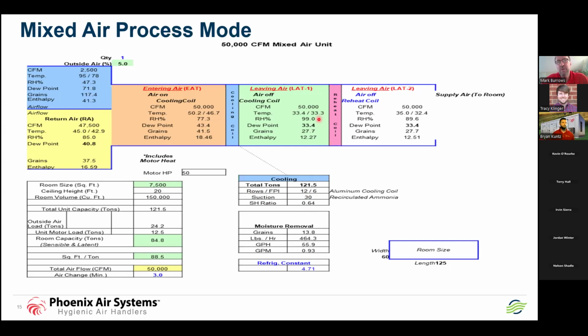Is this a safe configuration to deliver to the room? Well, look at the dew point. That's 33.4 degrees on the discharge dew point versus the room at 40.8. That is definitely what we see all day long as a safe configuration. Under these conditions, you won't see any vapor trails coming off the supply diffuser into the room, let alone condensation.